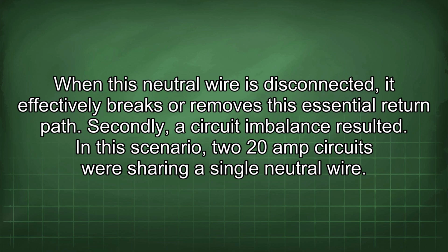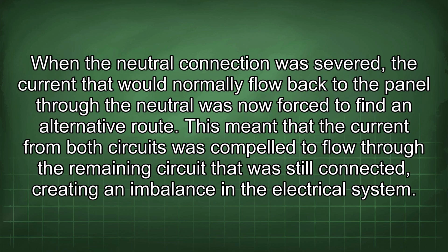Secondly, a circuit imbalance resulted. In this scenario, two 20-amp circuits were sharing a single neutral wire. When the neutral connection was severed, the current that would normally flow back to the panel through the neutral was now forced to find an alternative route. This meant that the current from both circuits was compelled to flow through the remaining circuit that was still connected, creating an imbalance in the electrical system.